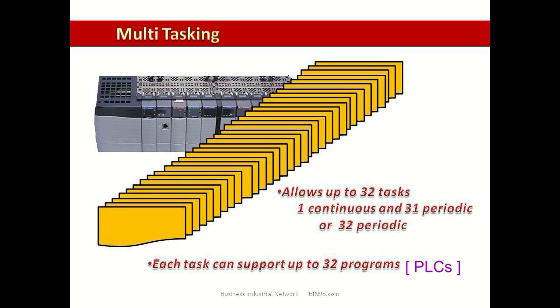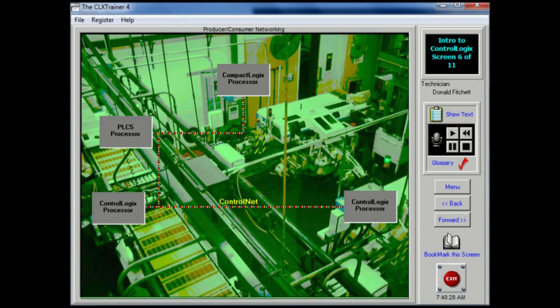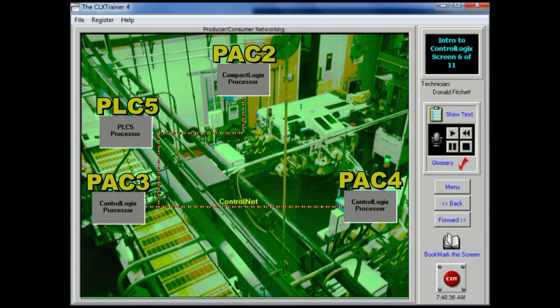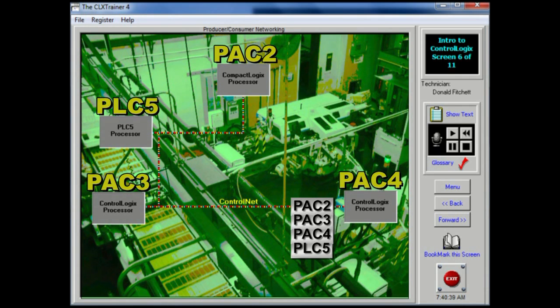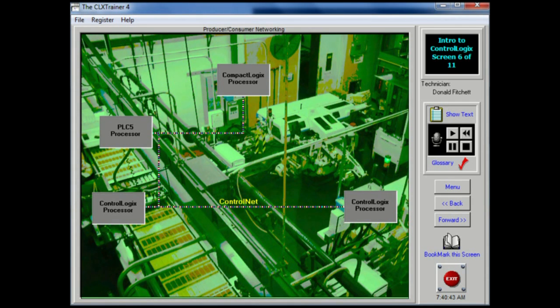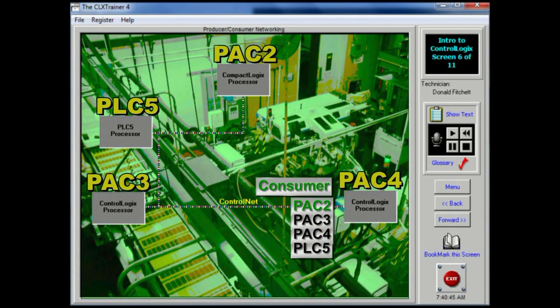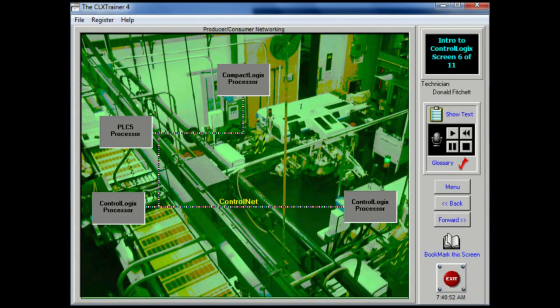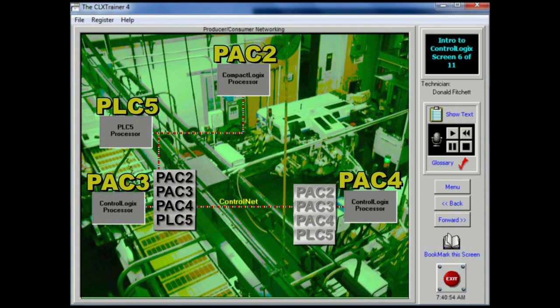Each one of these programs can have their own data and logic. The producer-consumer network model is used by the ControlLogix system. In this type of network, the producer places a connection ID at the beginning of the data packet. The packet or message is then multicast, and each module screens the ID to determine if it needs the data. If it does, that module becomes the consumer. This allows the programmer to have one or many modules listen for and consume data with a specific connection ID while discarding or ignoring all others.